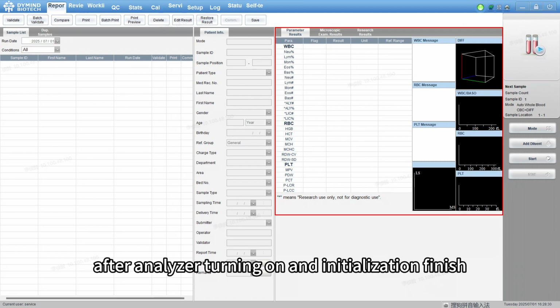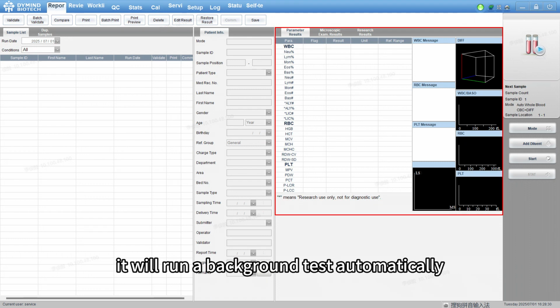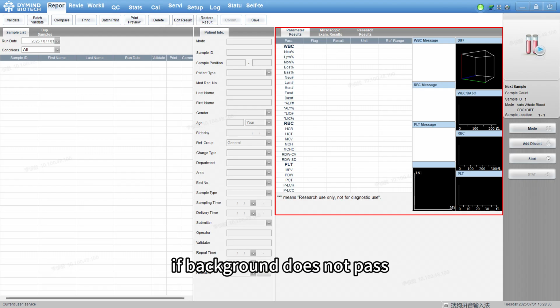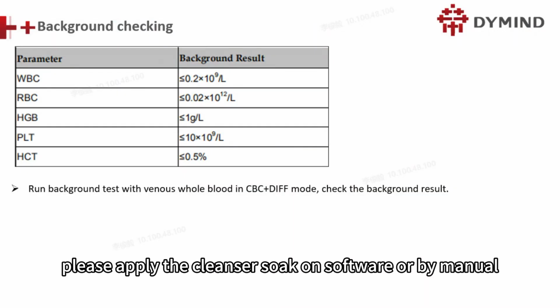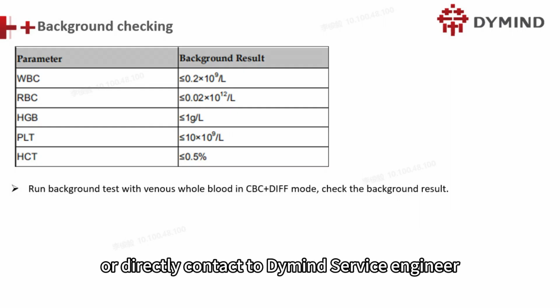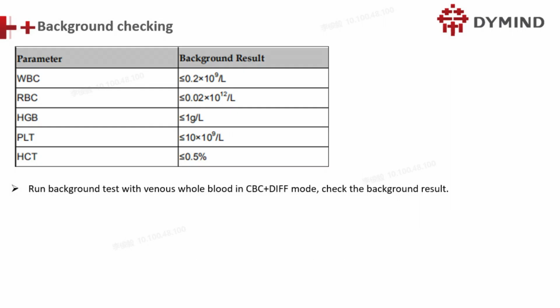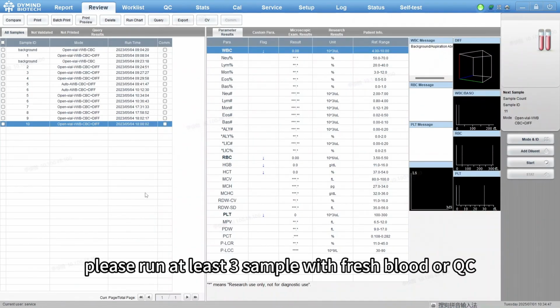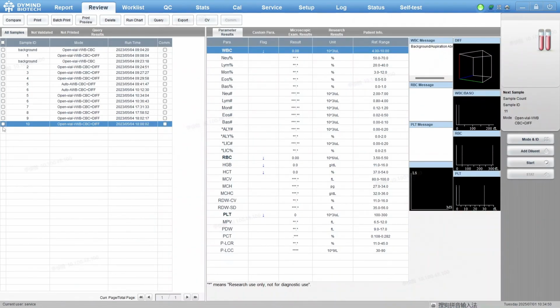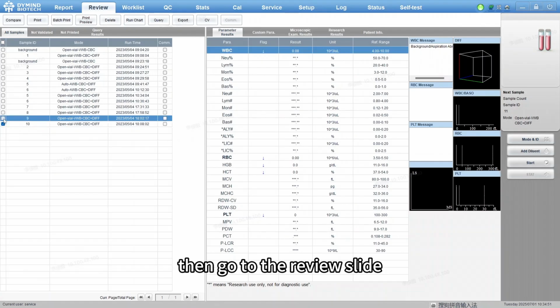After the analyzer is turned on and initialization finishes, it will run a background test automatically. If the background does not pass, please apply the cleanser soak in the software or manually, or directly contact the Dymind service engineer. After that, please run at least 3 samples with fresh blood or QC. Then go to the review slide.